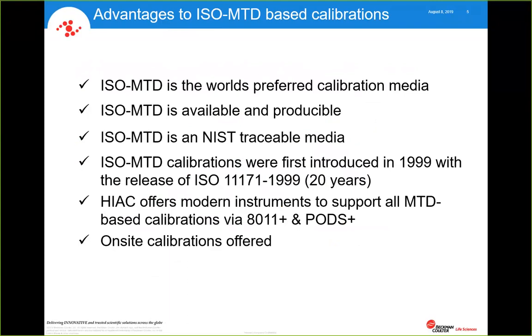That's why it's so crucial to transition folks from the old AC fine test dust calibrations to the new modern calibration, just so we have, basically, tracking and traceability and comparability across manufacturers, but also even within our own product offerings. With the HIAC, the modern instruments support the MTD calibrations. Again, with the 8011+ and the PODS+, we can actually report out to the old NAS 1638 standards and the NAVAIR standards. And of course, as always, we have global service with our products, and so we can actually offer on-site calibration at your facility, where you don't have to send your instrument in. We can come on site, perform the calibration. We're going to be in and out of there in a couple hours, generally.